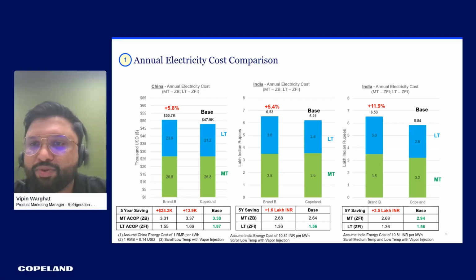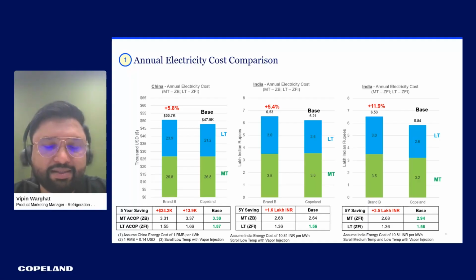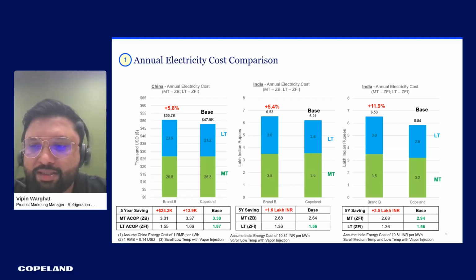And if we go to the extreme right, if we use vapor injected scrolls, then you can achieve even double the savings. So 5.4 becomes 11 to 12% of savings. That is the amount of saving this scroll can deliver versus the existing technologies available in the market. And by the way, the solution that you see, which was on the previous slide, is actually a scroll compressor based rack system versus the semi-hermetic compressor based rack system.